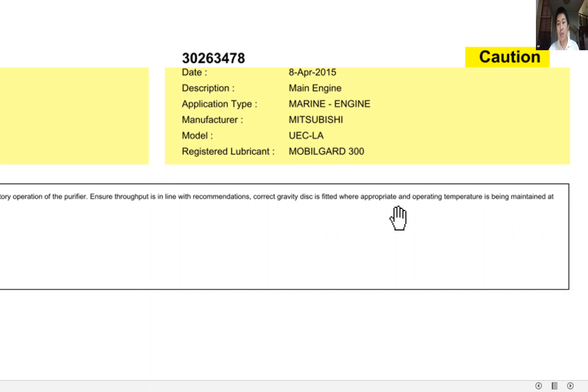So for example here, the water content of this crosshead engine system oil is marginal. Check satisfactory operation of the purifier. Ensure throughput is in line with recommendation. Correct gravity disc is fitted where appropriate and operating temperature is being maintained at 90 degrees Celsius. So they put the remarks here.